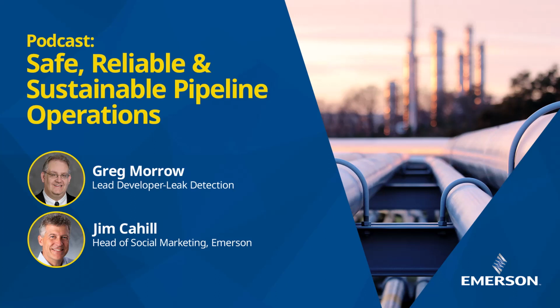Sensor quality is also a factor. If your pressures report by exception at 0.1 bar, which is a pretty big step, you're not really going to get good results modeling slow drifts and sharp transients. Temperatures are also very important depending on the fluids you transport. Some of them, like gas, can be extremely sensitive to temperature. So good temperature measurement is important.